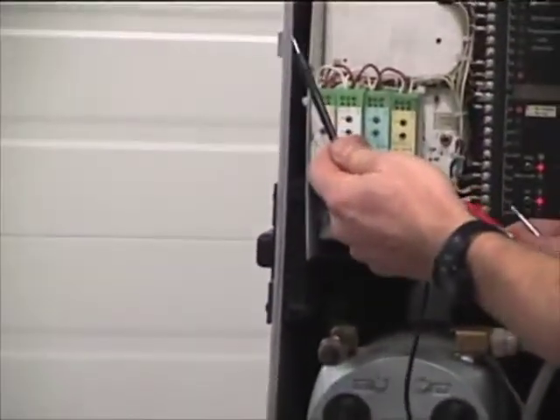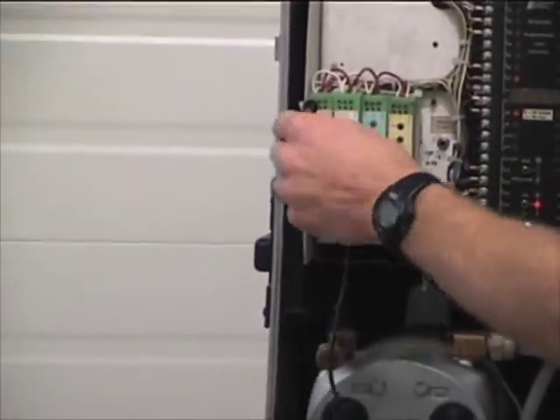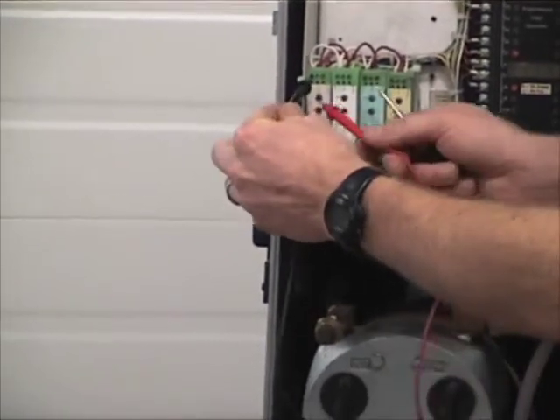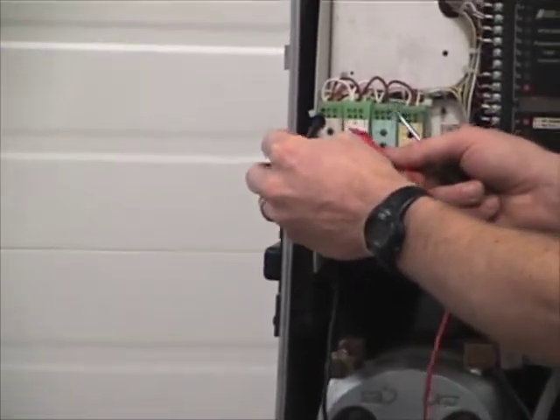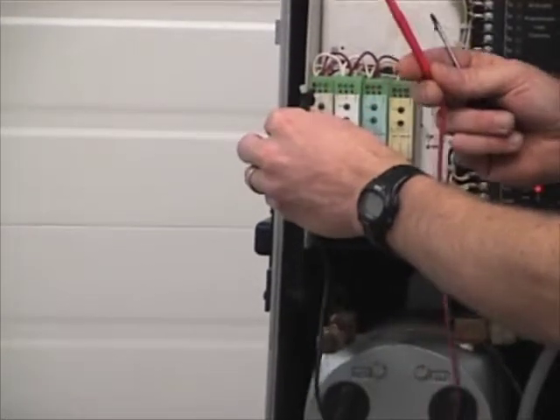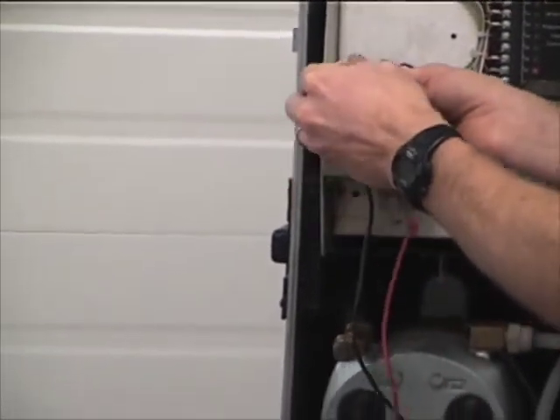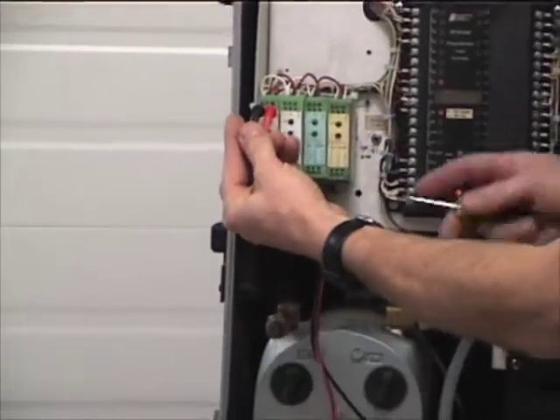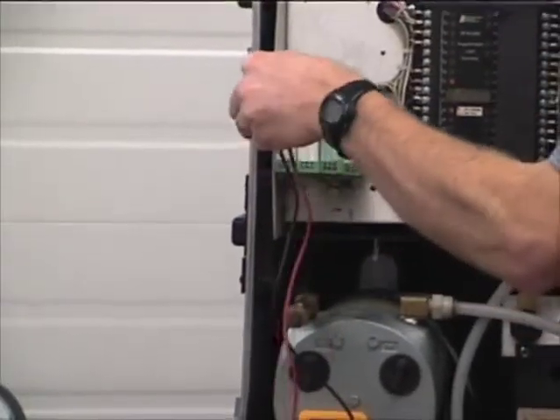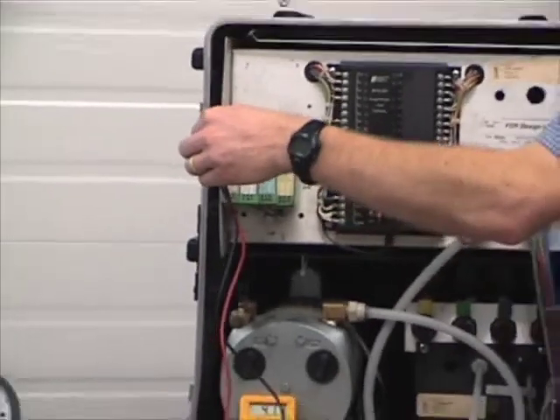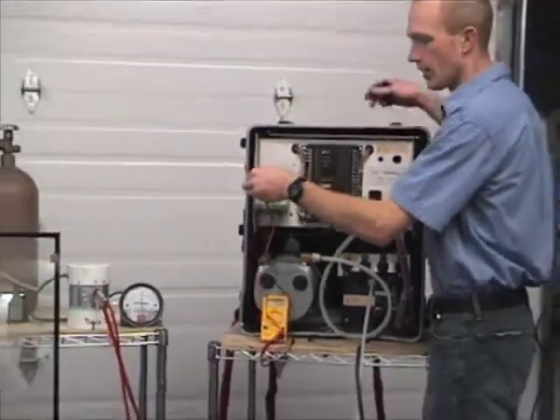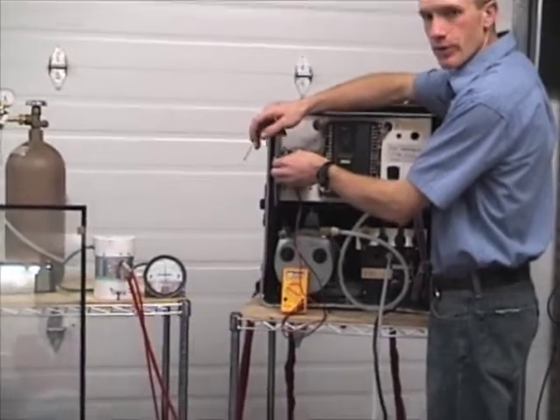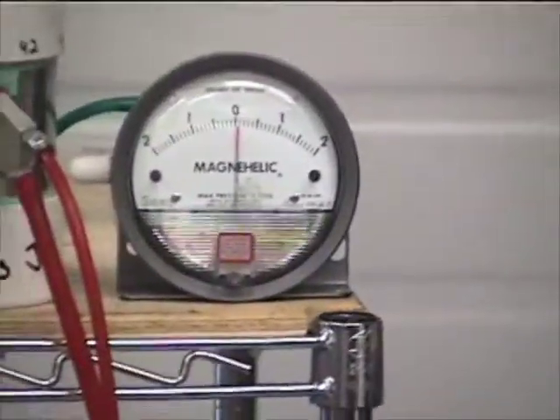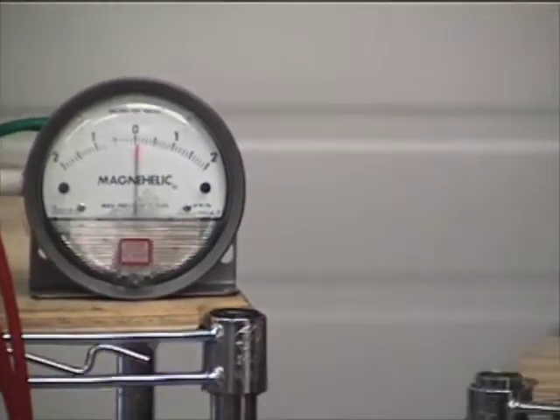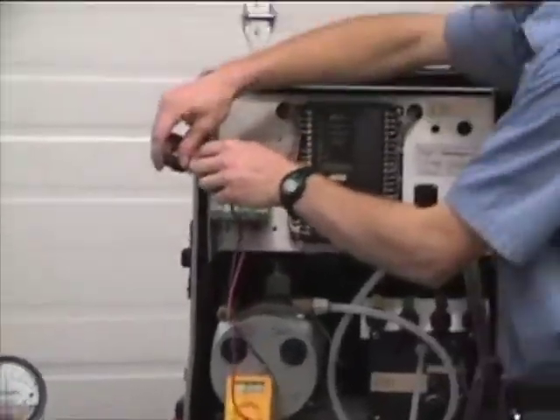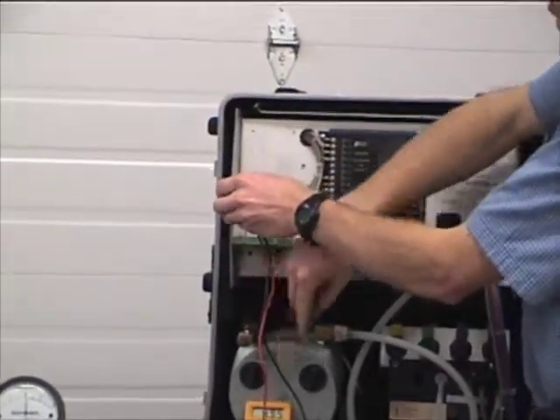I want to take my black lead and put it on the common, again on the same amplifier board that I previously adjusted. And then my red lead on the output screw, and you can see it's just right in the screw terminals. Then I want to start the line again, and I'm going to confirm that I still have a positive pressure on the magnehelic, and then I'm going to do one adjustment here on this potentiometer to get 5 volts on my voltmeter.